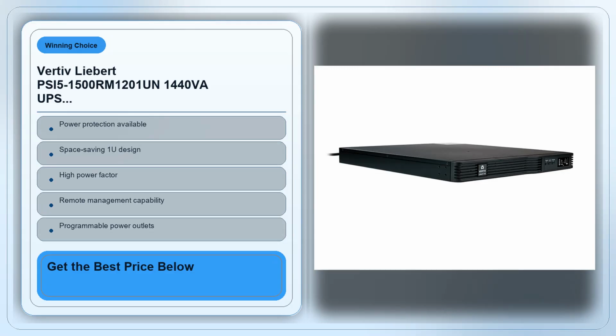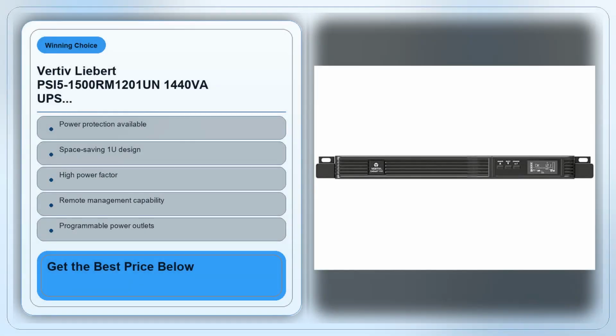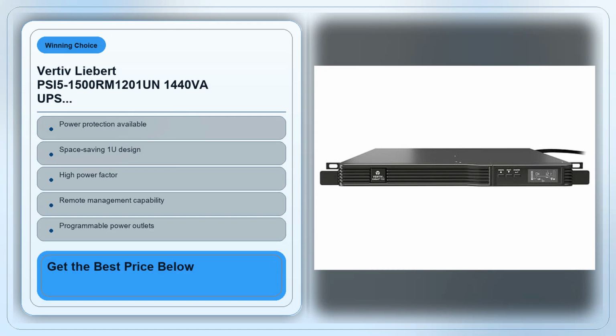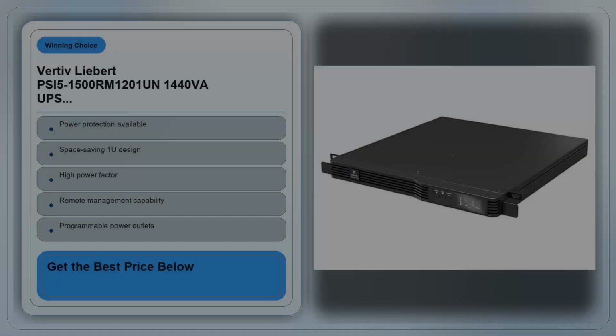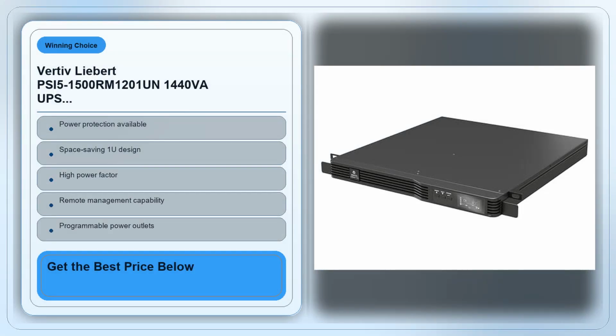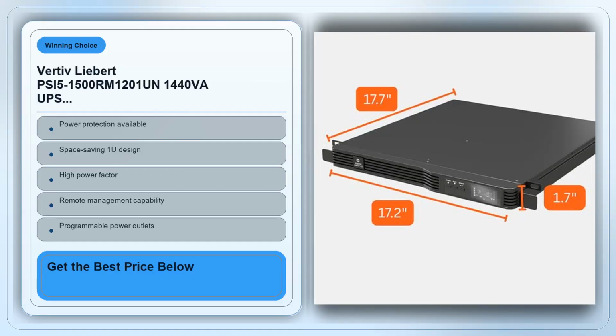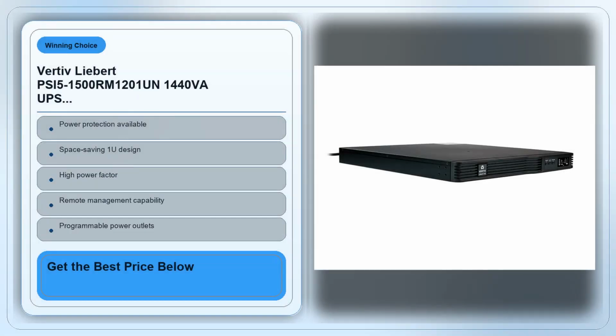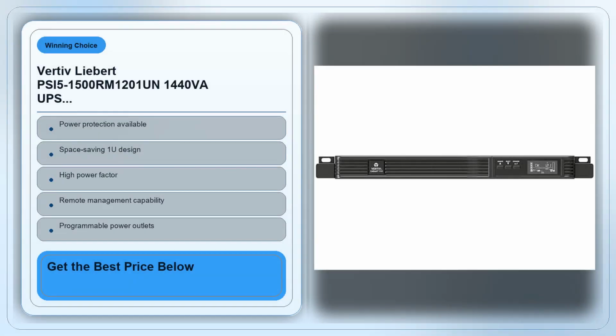On the flip side, if you're looking to protect a whole floor of equipment or you need more than 10 minutes of runtime under full load, this UPS will feel cramped. Its battery capacity, while decent for its size, won't keep a heavy load rack humming for long. Also, because it's a 1U design, you lose the luxury of internal redundancy. You get a single power module, so if that module fails, the whole unit is out. For enterprises that demand N+1 redundancy, you'd be better off stepping up to a larger, dual-module system.